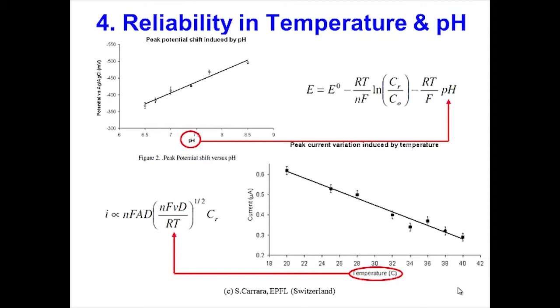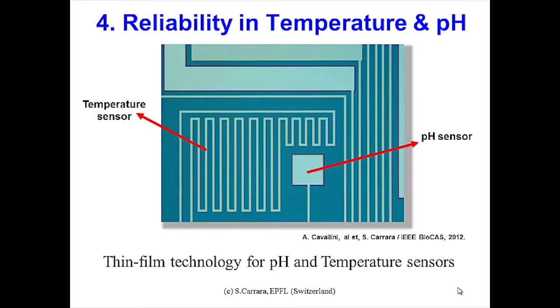We integrated, with thin film technology, just a resistor in platinum on the platform to realize the temperature sensor. Then we realized a junction facing platinum and iridium dioxide in order to obtain a pH sensor, because this junction is very sensitive to the pH. This is just one experiment in which we acquired the open circuit potential, injecting NaOH into the solution in order to move from low to high pH, and then we injected hydrochloric acid in order to move from high pH to low pH. And as you can see, the sensor registered all this variation quite well, and if we look at the calibration curve, we see that they are extremely linear, both moving from acid to basic and moving from basic to acid.